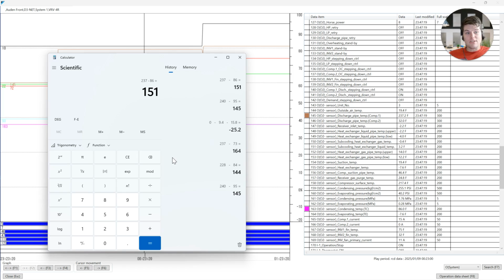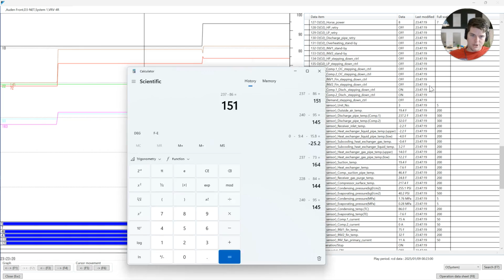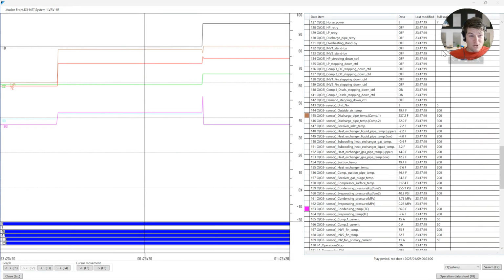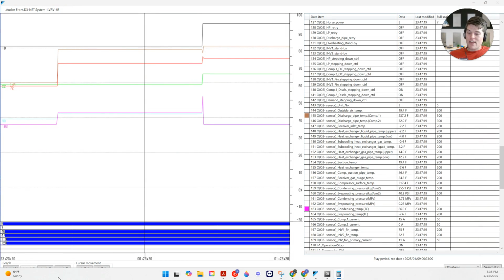Suction superheat, we take the larger number first, which is going to be what? It's going to be your suction line temp and then your saturation temp, right? Those are the two that we want to just make sure that we're not mixing up here. Understand what numbers we're doing and how to do it so that we get the right numbers. 151, my gosh, that is hot.